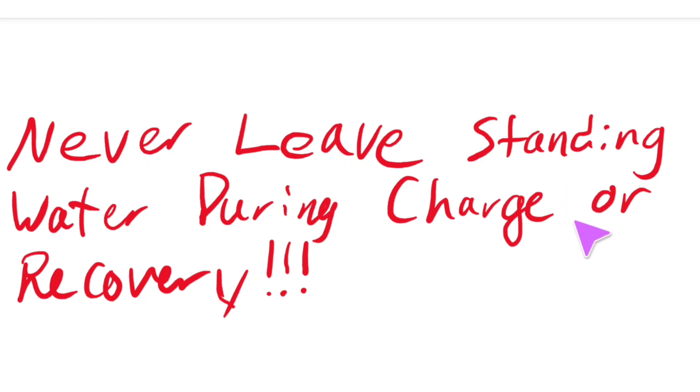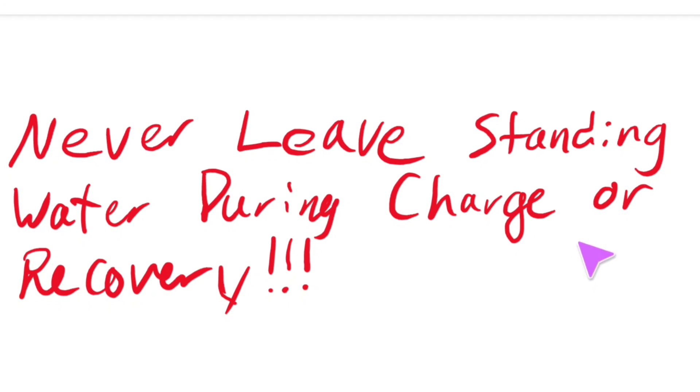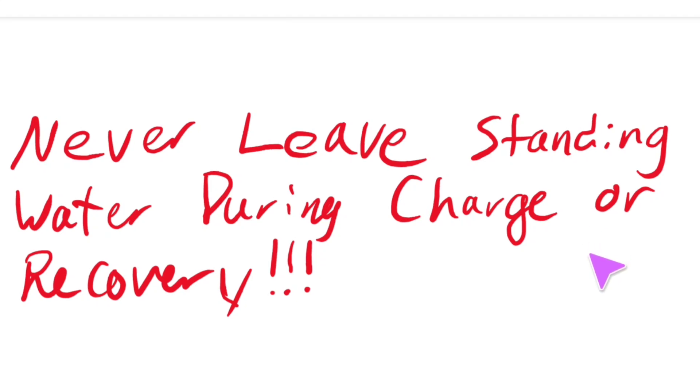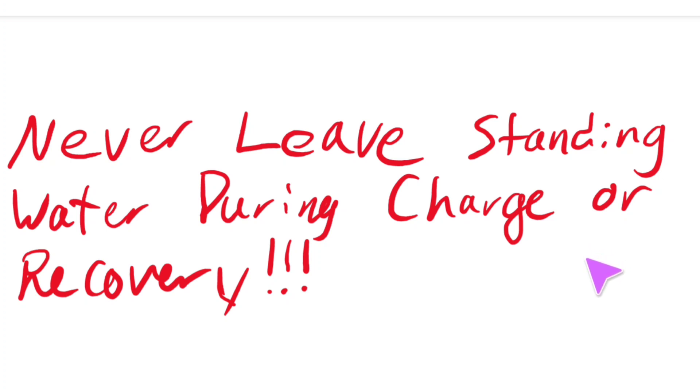As you see on the note here, there is an extremely critical thing to be aware of: at no point do you ever leave standing water resting inside of the tubes during a recovery or charge procedure. You always want to make sure that water is either flowing or has been drained out entirely. I personally practice flowing the water through the tubes. The reason for that is strictly for adding heat to the refrigerant. As you recover, you have to boil the refrigerant off as vapor. If you flow water through the tubes during the recovery process, it helps the refrigerant to boil easier, which keeps your pressures higher, compression ratios lower, which increases your flow volumes. This is extremely important.